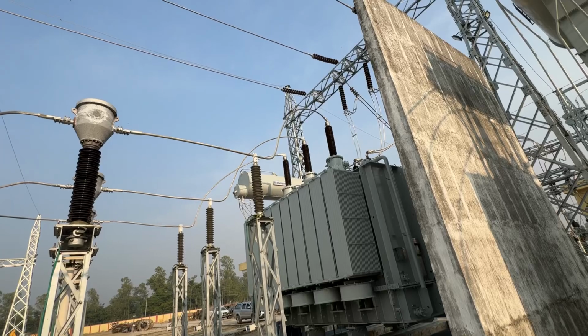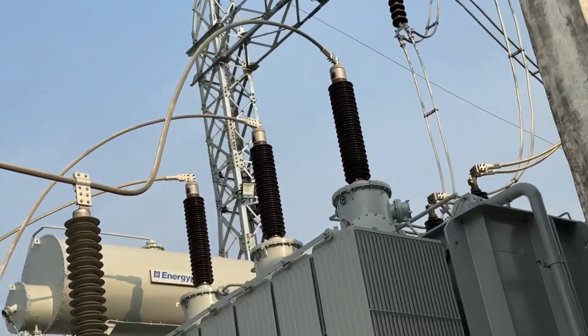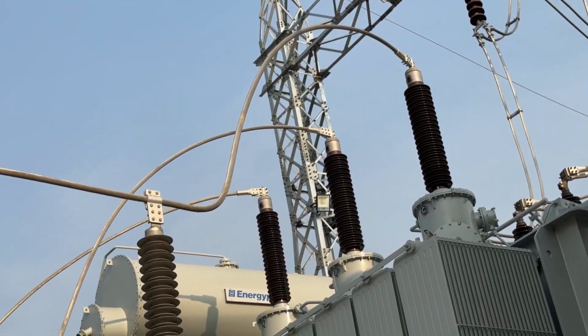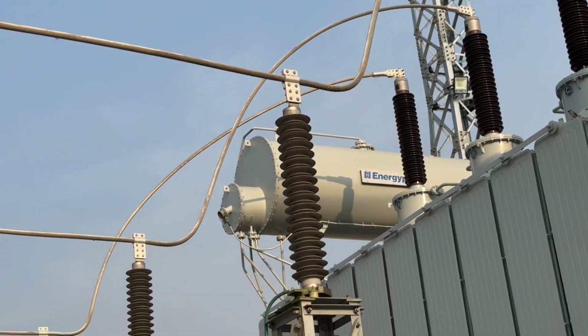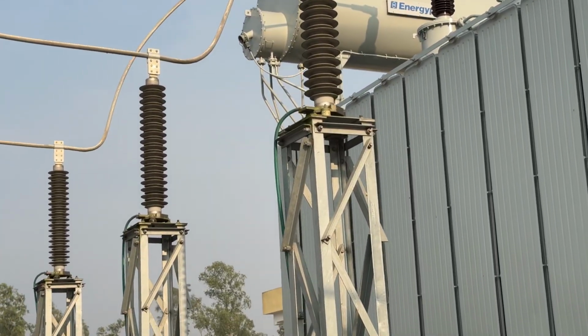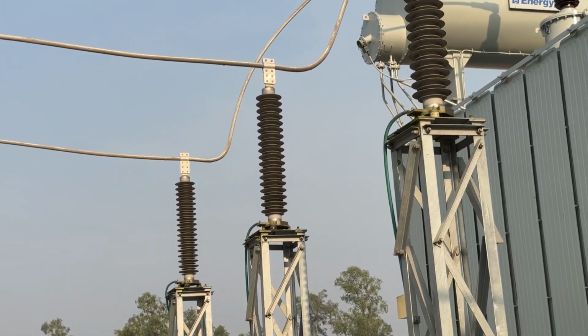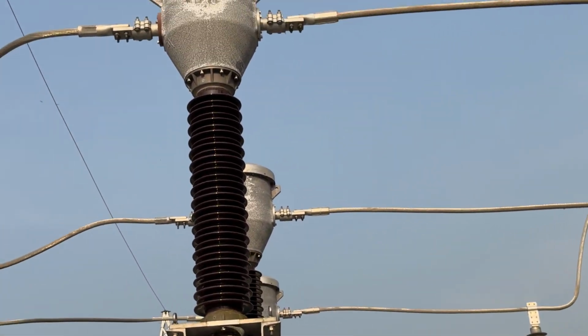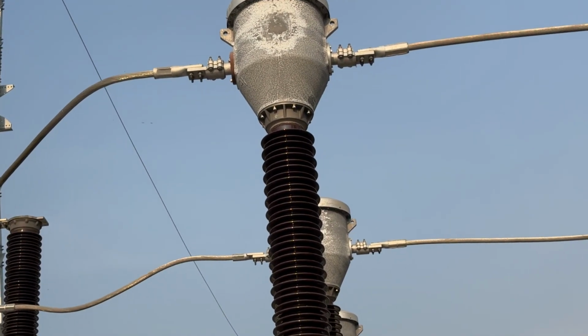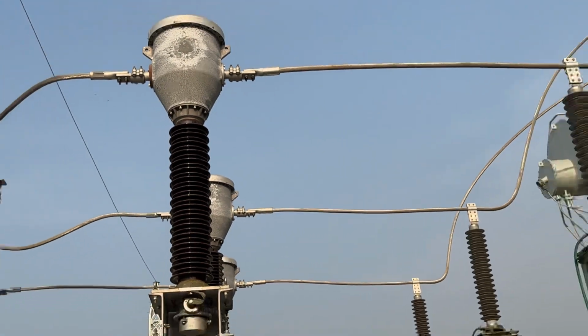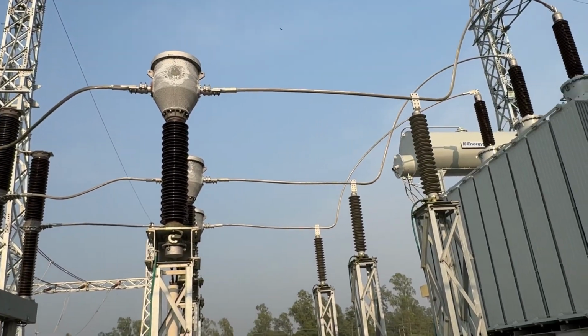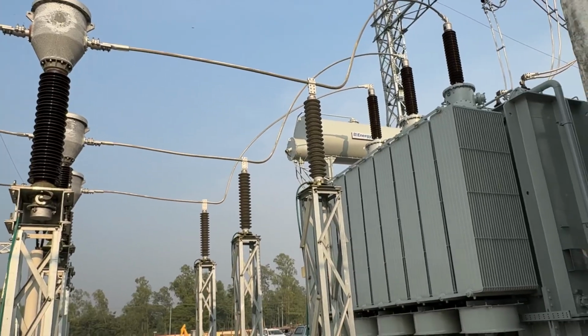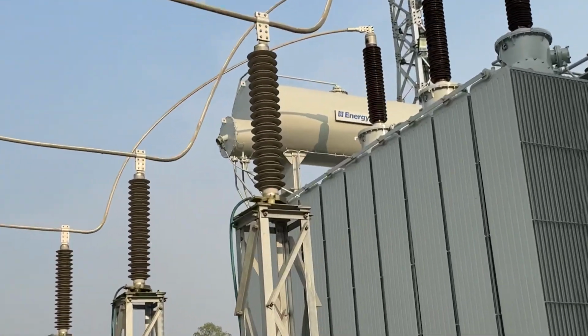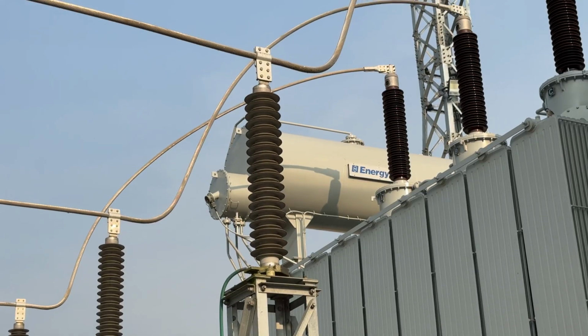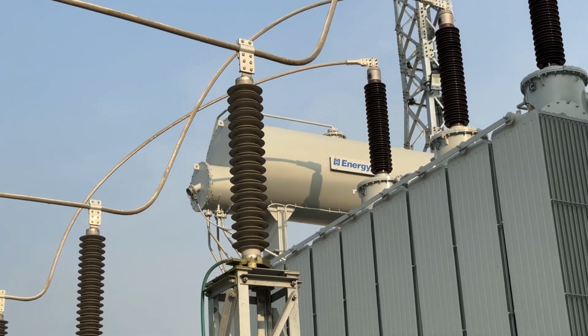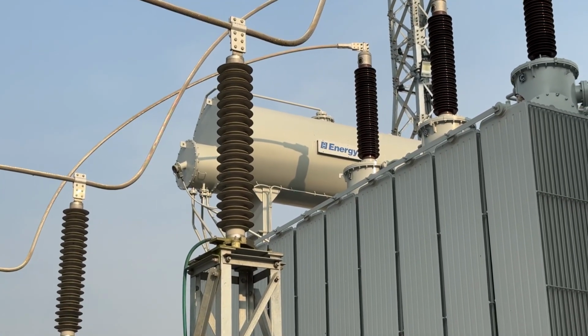That side is the high side of the transformer, the high side bushing. Near the bushing there is a lightning arrestor. Any switching impulse from circuit breaker switching or thunder, every time this type of impulse will be arrested by this lightning arrestor. There is also an arrestor at the secondary 33 kV side.